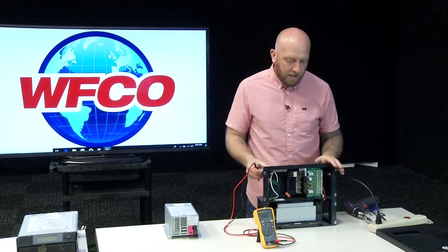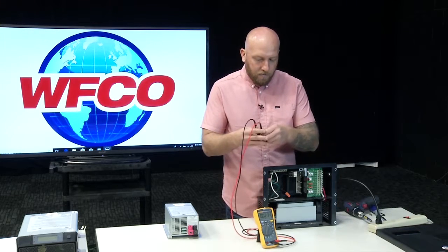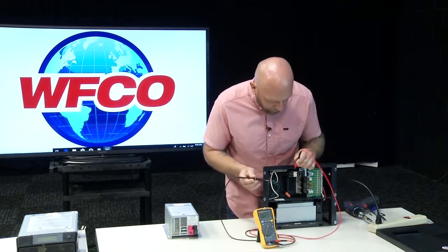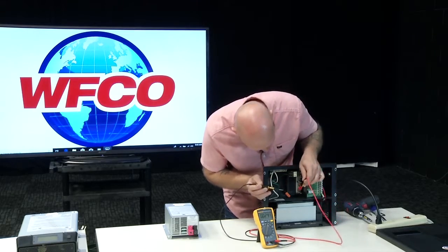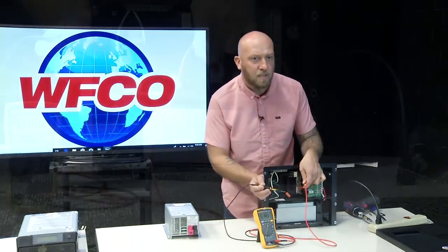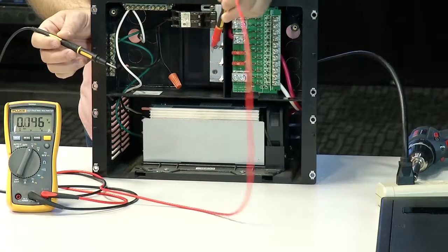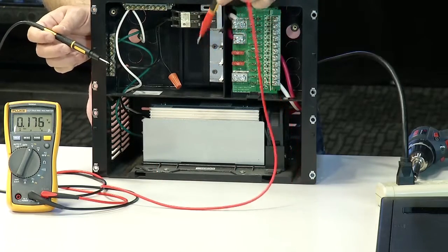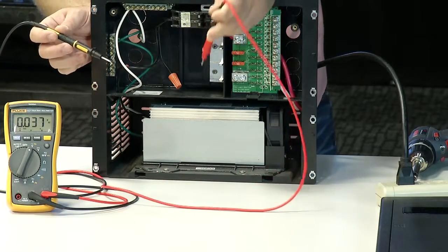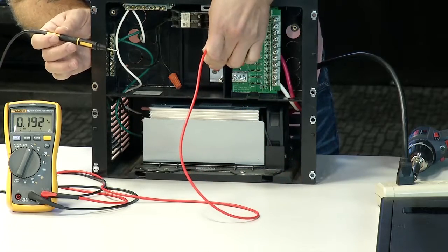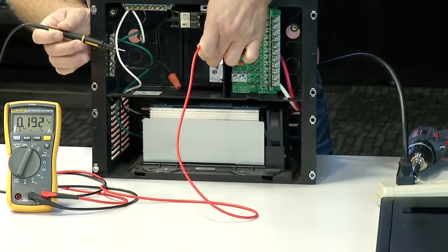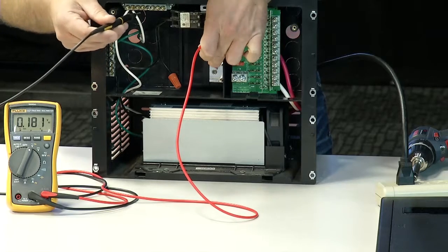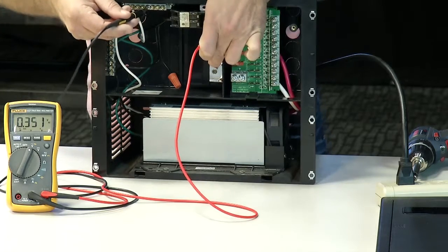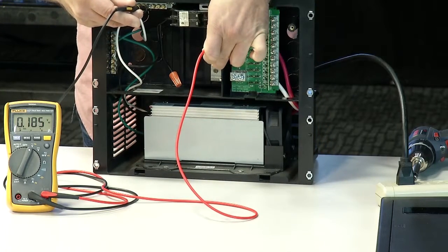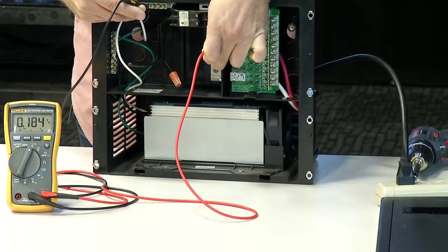My breaker is off right now, so assuming this is not hot, I would test the AC busbar that's in the panel itself. It's this metal bar right here with all the stabs where the breakers are actually located onto. So to ensure that I don't have voltage coming through, I'm going to test from the busbar to my neutral bar, and I should have nothing, which I have 0.1, so that's good.